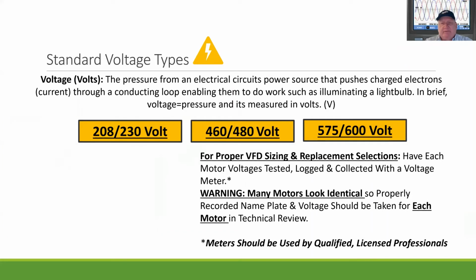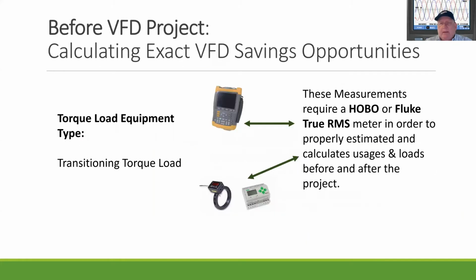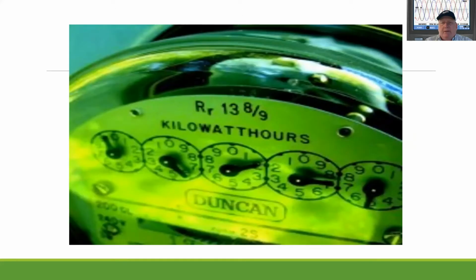These are some of the standard voltages that we have in America: 208, 230, 460 volt, and 575 and 600 volt power. That's the input power. Again, we want to make sure that we have the proper metering technologies to find out what the true RMS power is of that motor and application. The ultimate goal here is to slow this meter down.